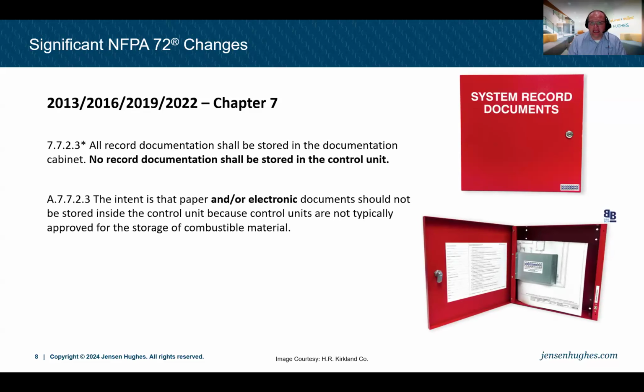Rather, a documentation cabinet should be stored or be provided adjacent to that control unit that contains all the paper or electronic documents that maybe technicians used to store inside that fire alarm control unit. And the nice thing with these documentation cabinets, like you see on the screen here, is most of them have a hard drive, a little built-in USB drive that can be used to store electronic documents, things like inspection reports, impairment reports, deficiency reports, basically the system programming, the as-built drawings, everything can be stored electronically, and it's sitting right with the fire alarm control unit, and everybody knows where that material is.